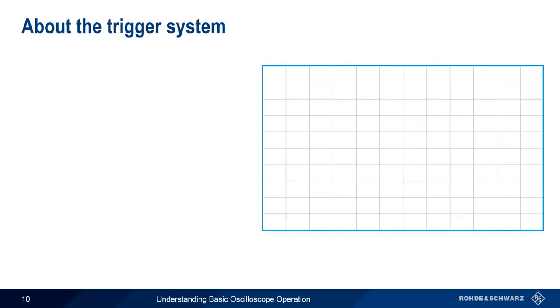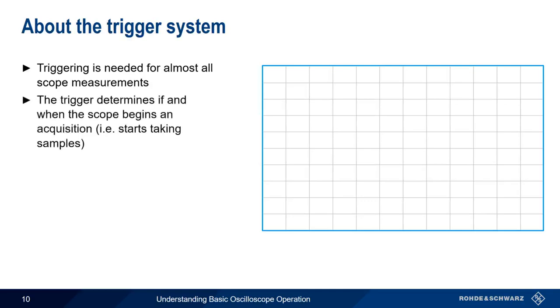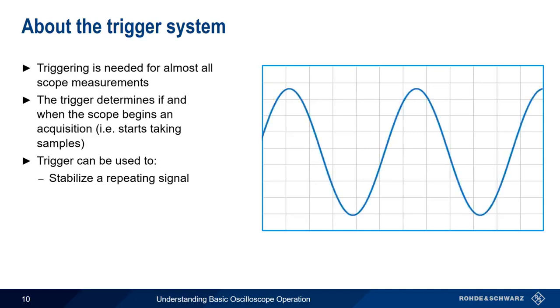The trigger system is extremely important because triggering is needed for almost all oscilloscope measurements. Essentially, a trigger defines the conditions that have to be met before the scope begins an acquisition or begins taking samples. Triggering can do two different things. First, it can stabilize a repeating or periodic signal, such as a sine wave, by causing each sweep to start at a given point on the signal.